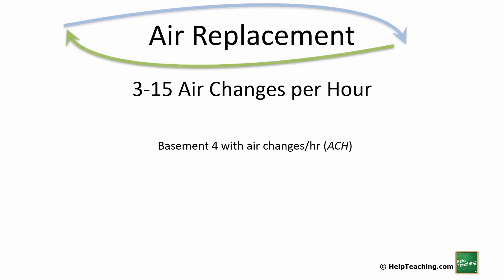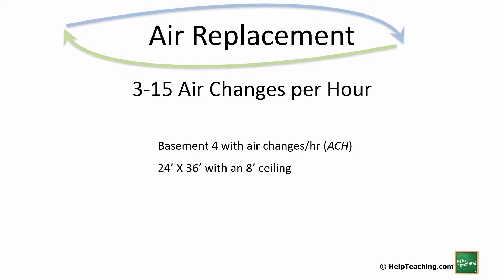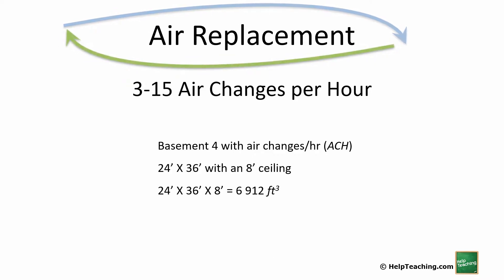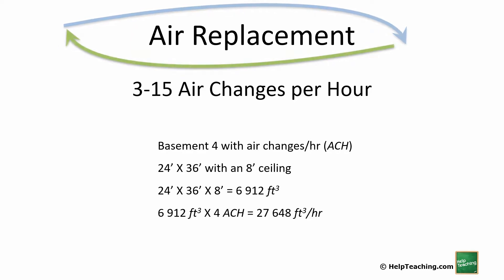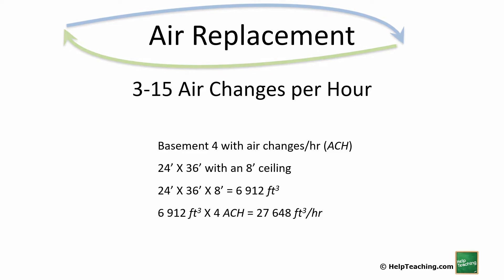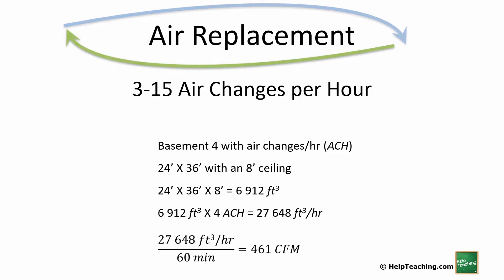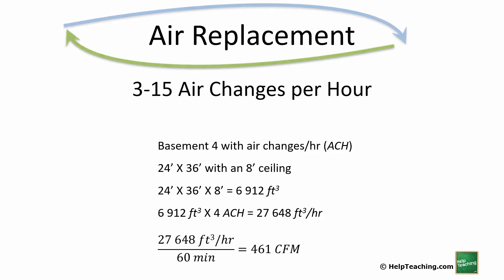Our first example is a basement with 4 air changes per hour. The basement is 24 by 36 feet with an 8-foot ceiling. To calculate the volume: length times width times height — 24 times 36 times 8 — gives us 6,912 cubic feet. We want to change that air four times in an hour, so we multiply by 4 and get 27,648 cubic feet per hour. Dividing by 60 minutes gives us 461 CFM — cubic feet per minute — which is the unit that pretty much all fans use.